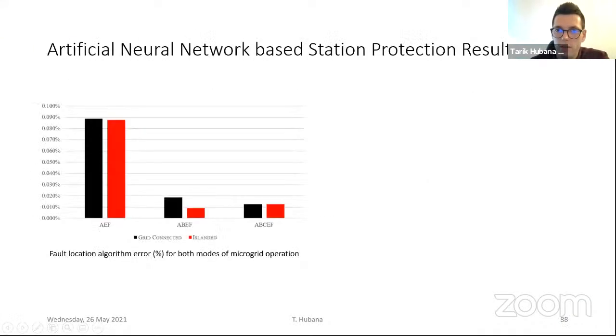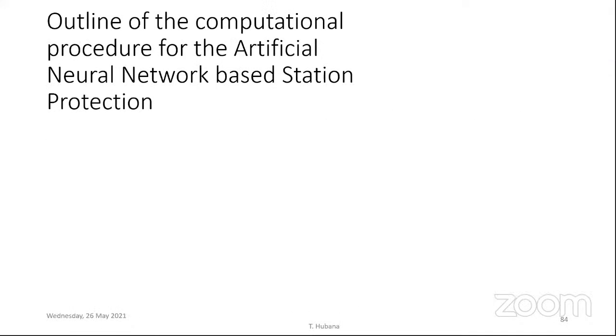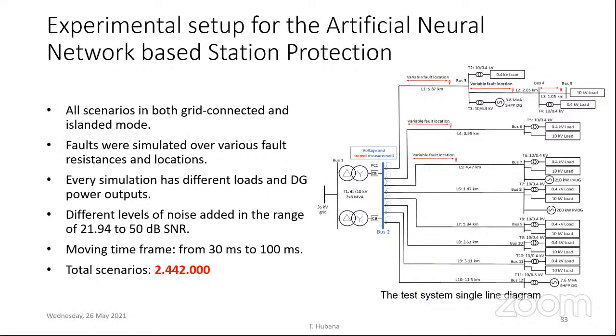No, actually, it is part of the same training, and I will go back to that slide. The training procedure steps will be the same, but the methodology may change. Actually, there are three different methodologies here. The first one is used to detect the fault and classify the fault type. The second one is used to detect the faulty feeder, and the third one is used for each of these feeders to estimate the fault location.